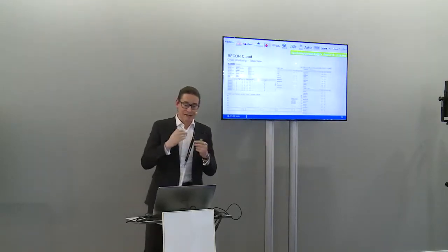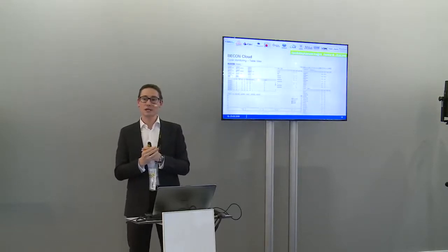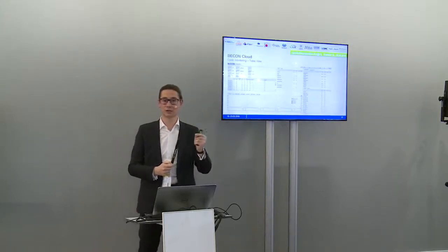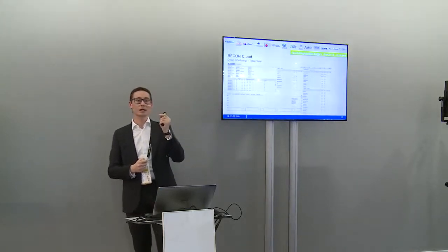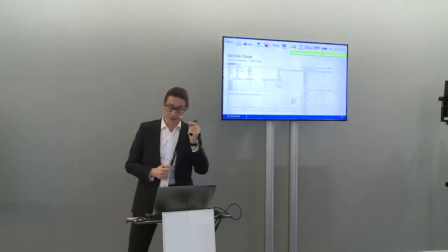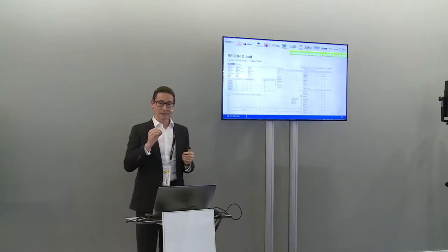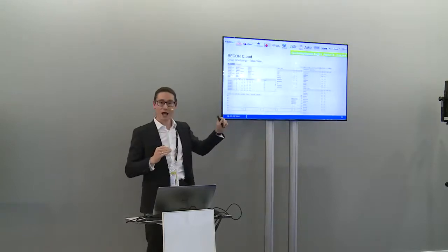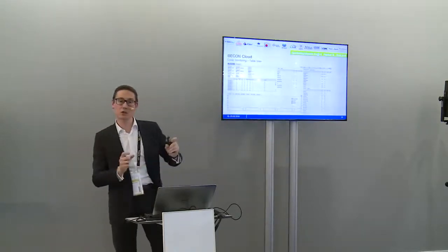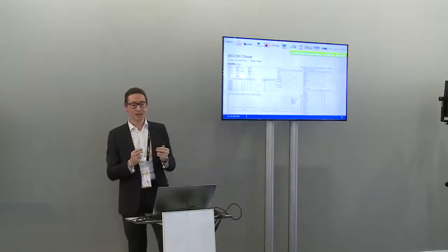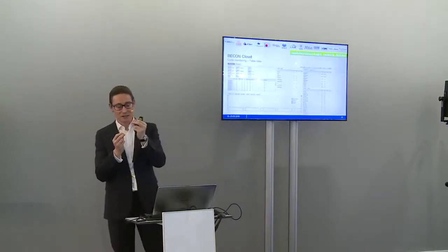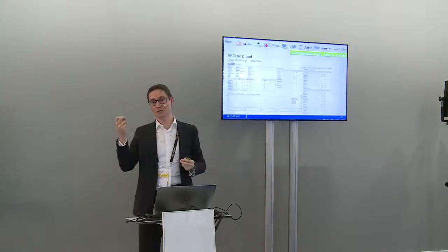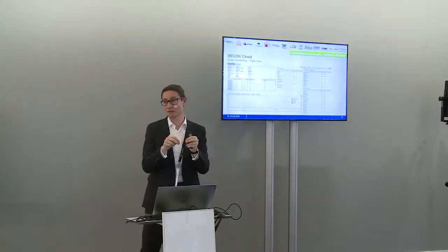But also, we can give really important information to the VRF installers or maintenance. This is the cycle monitoring. The cycle monitoring is a really important monitoring specification that we have in that device, because the people that have deep knowledge of the VRF solution can perfectly know what is happening if the high pressure goes over the limits or the compressor frequency is going so high. It means the people that analyze this information can make a prediction of what should be the problem in the future or the problem that we are having now in the installation.